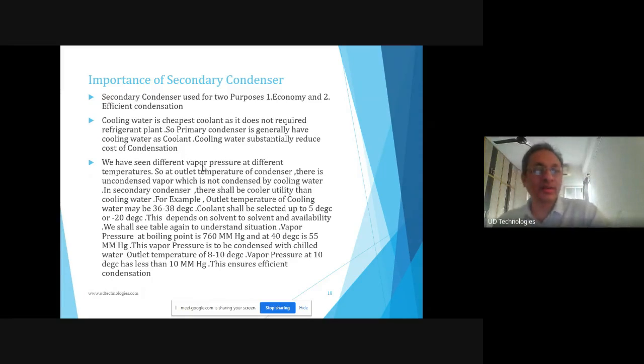Now we'll come to the secondary condenser. Why is a secondary condenser used? It is used for two purposes: one is economy and the second is efficient condensation. We earlier discussed that generally cooling water is used in the primary condenser, and in the secondary there will be either chilled water or brine. Why cooling water? Cooling water is the cheapest coolant as it does not require any refrigerant plant. The cooling tower is used on the principle of simultaneous mass and heat transfer with the air, so there is only the cost of the fan. No refrigerant, so the cost of cooling water is very low, and to reduce the cost of condensation, cooling water is used.